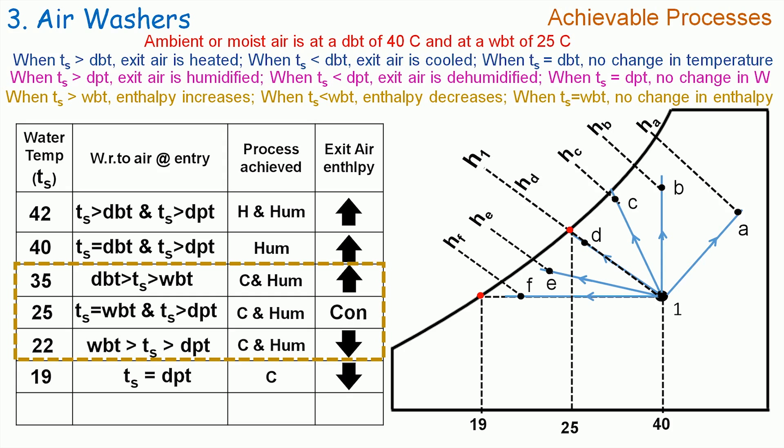Let us now supply the spray water at 15°C. Here TS is less than dry bulb temperature, hence air is cooled, and TS is less than the dew point temperature also, hence air is dehumidified. Therefore, the achievable process by the air washer is cooling and dehumidification. If we plot it on the psychrometric chart, then the process 1G will be representing it. The enthalpy HG is less than H1, hence the exit air enthalpy decreases. These are the various processes that are achievable with air washers.